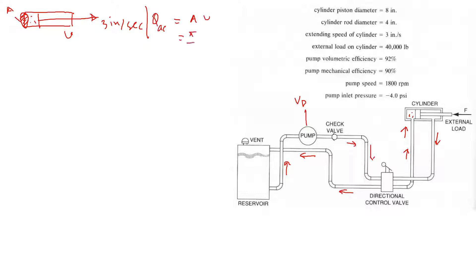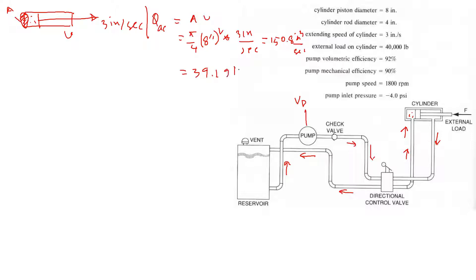The area is (π/4) × D², where D is 8 inches, multiplied by the speed of 3 inches per second. Solving this gives 150.8 in³/s. Converting to gallons per minute, that equals 39.2 GPM. So the actual flow rate is 39.2 GPM.